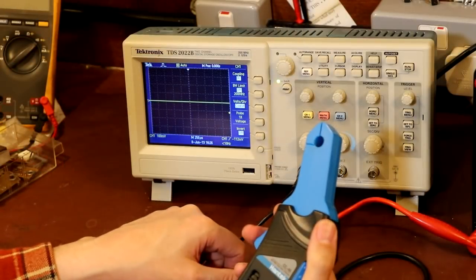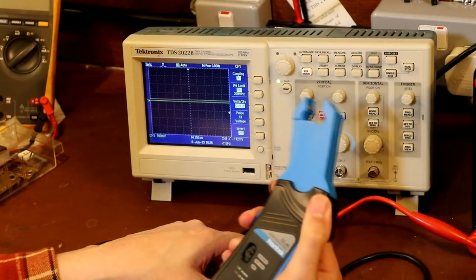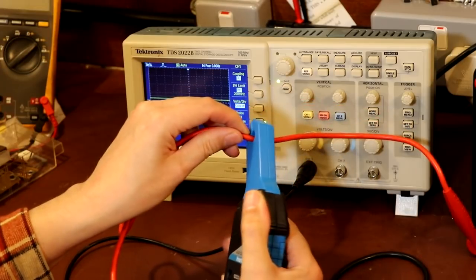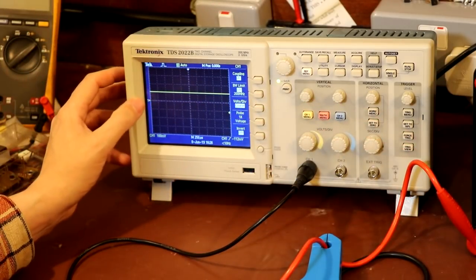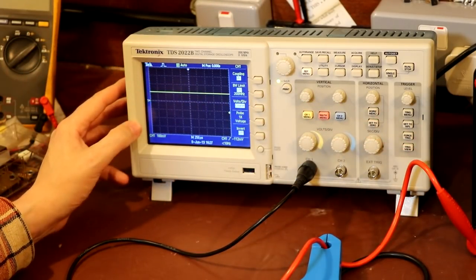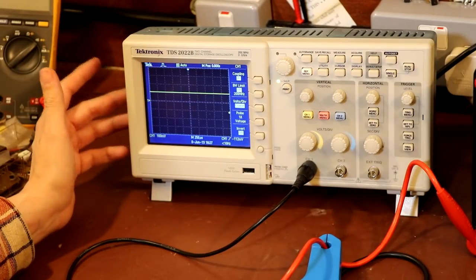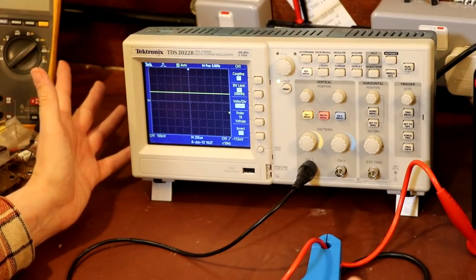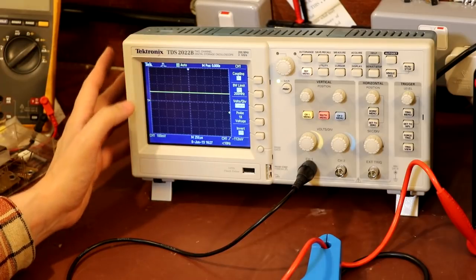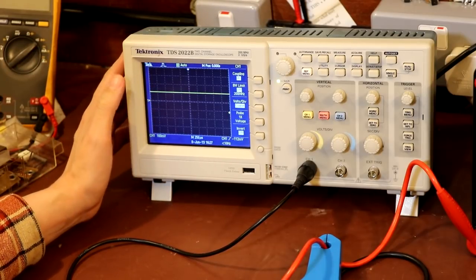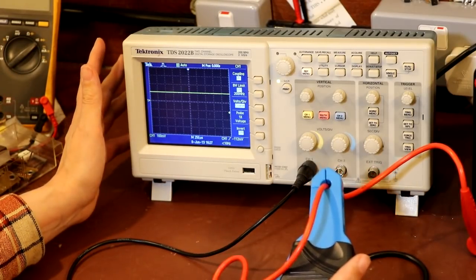So I'm going to open up the clip on our clamp meter by pulling the little trigger, then slip the wire through. Hopefully you can see it's gone up by 1 division, which is 100 millivolts. The number of divisions of deflection is proportional to the current going through the clamp meter.